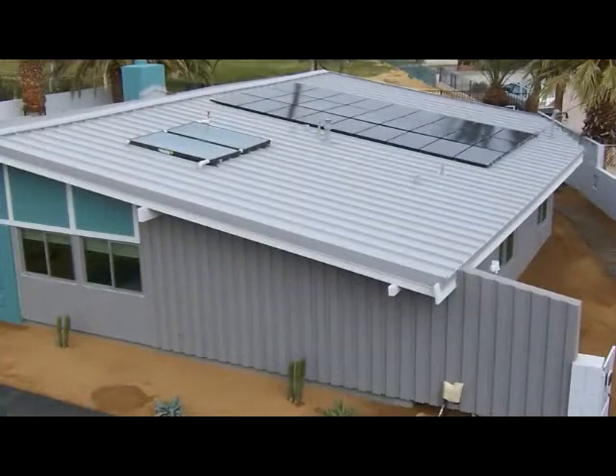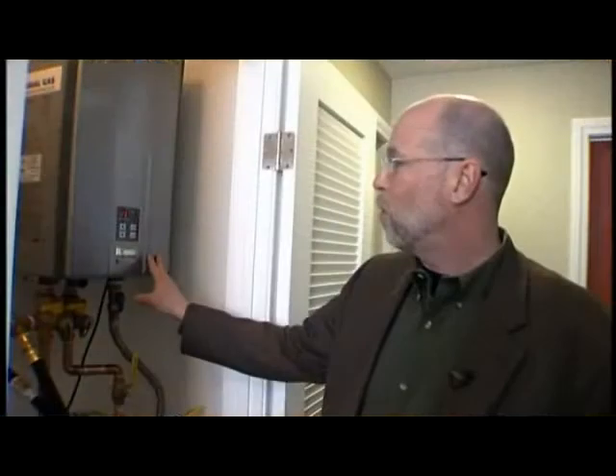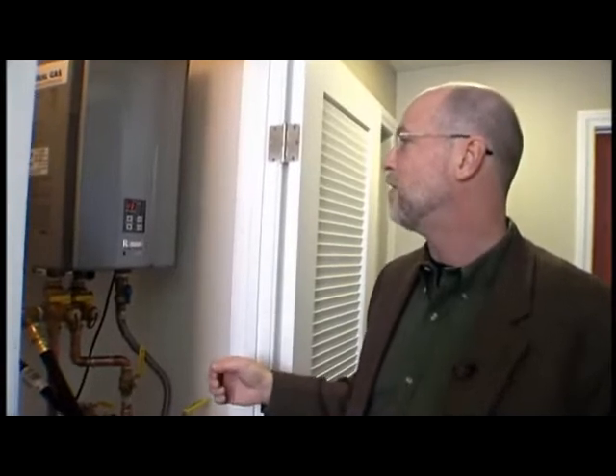When I turn on a hot water faucet in the kitchen, that water flows from that storage tank through my Rinnai tankless water heater. If the water temperature is not high enough, the Rinnai will automatically turn on and boost that water up to the desired temperature and deliver it to my kitchen sink or whatever other domestic hot water use I've got involved at the time. If that water is hot enough, it'll just simply pass through without firing, increasing my efficiency.